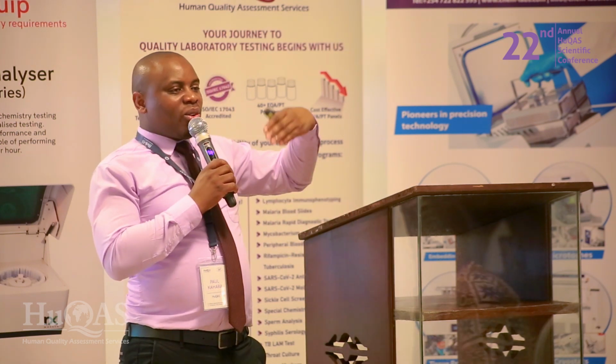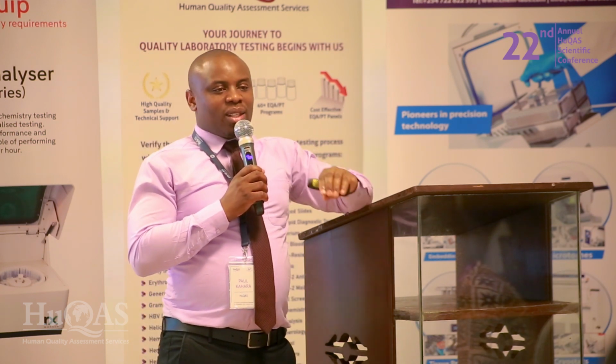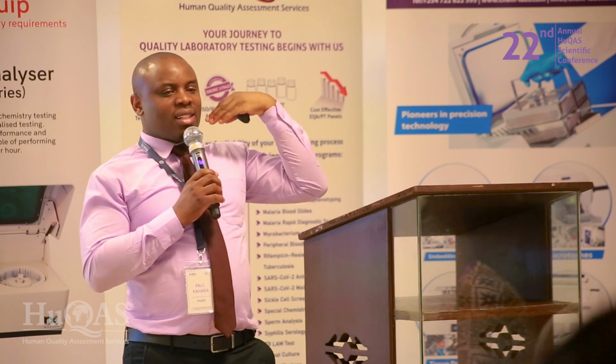Now we are told you must consider the use of third-party IQC materials, either as an alternative to what the manufacturers have given you, or in addition to what the manufacturer will give you for a particular analyzer, you must ensure that you run third-party controls. Now, which one is easier? Is it to do the two of them, or to use it as an alternative? I leave that to you to answer.